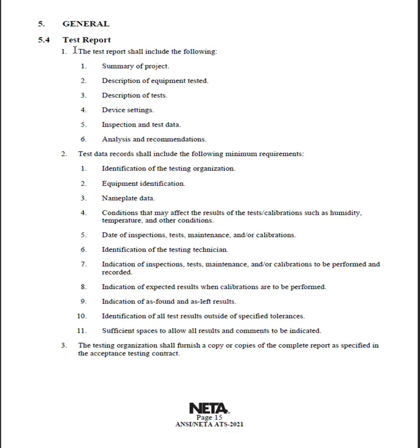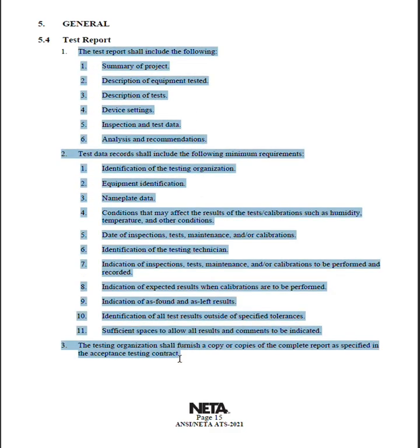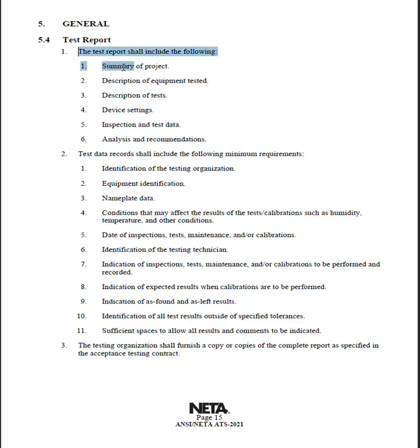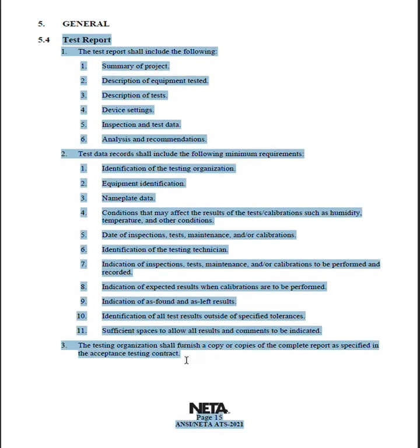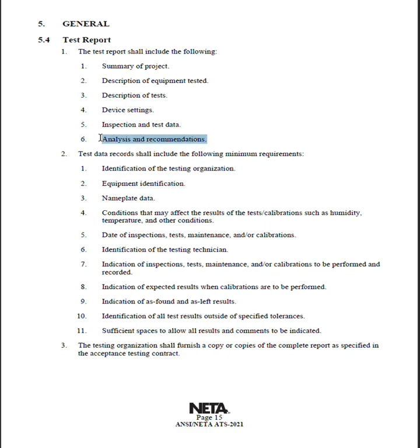The next thing, test report. This is a big one. I could talk about this all day, but I'm not going to. The biggest things I want to talk about on here are they should include the settings, right? So if your guys are filling out reports in the field and your test reports come back with a lot of blank information, that means they're not doing their job. Okay? Hands down, they're required to fill out the settings. Okay? Even analysis and recommendations are required on the report.